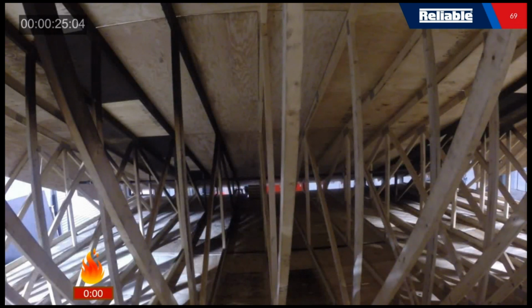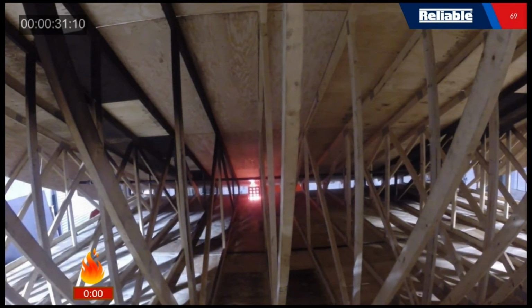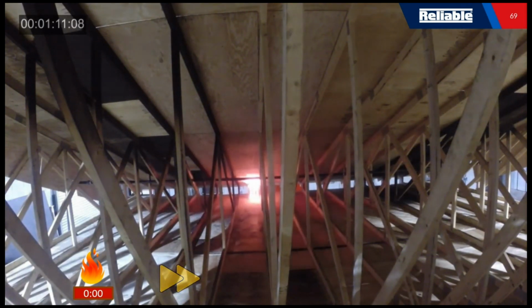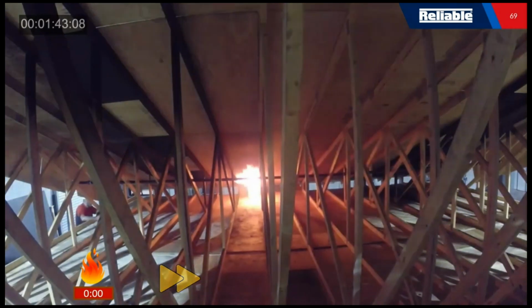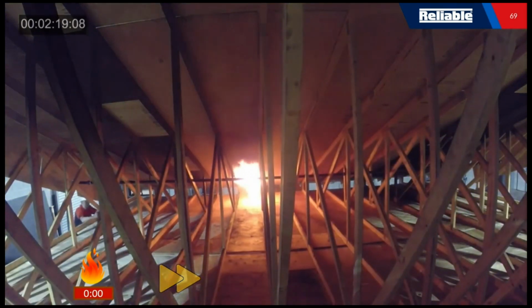We have a test video here showing you these sprinklers. Basically, we light a fire down at the eave. It's the furthest point away from where the sprinkler's installed at the peak. You're going to need this fire to generate enough heat to get up here and activate the sprinkler. Then the very unique spray pattern from these products is going to project that water down towards there and control and contain the fire.